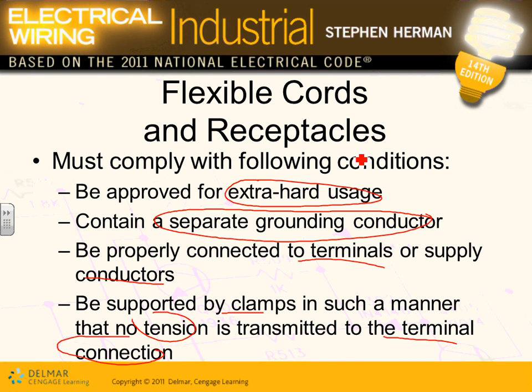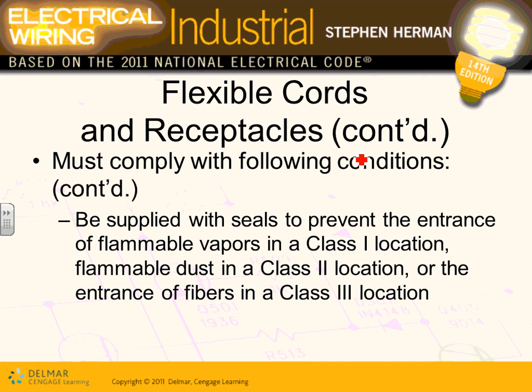So no transfer. The extra hard use cords have extra ground terminals. They have to have some clamps to support the flexible cord so it doesn't transfer the tension into the terminals. And also you have to provide a seal so the gases or the vapors or the dust cannot transfer through the cable or through the flexible cords. So they have a seal on them.